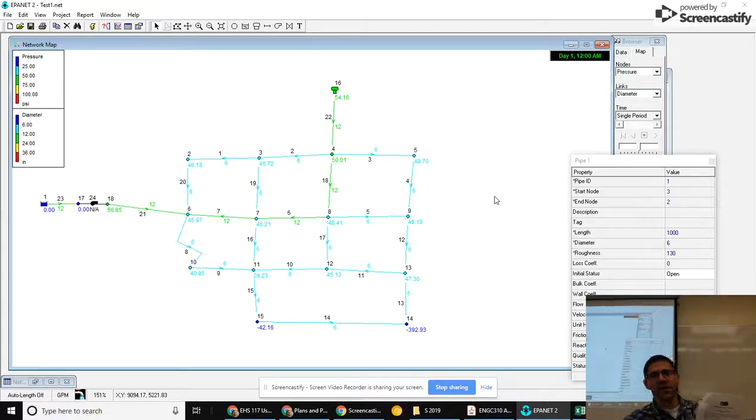There's a little note on there that for that one, EPANET won't let you run a simulation if there is no reservoir anywhere in the network. And this figure in your book has no reservoir. So it just has a note to say, add a reservoir, connect it with a link to this, and then close that link. So it's not participating, but now it can actually solve the problem.